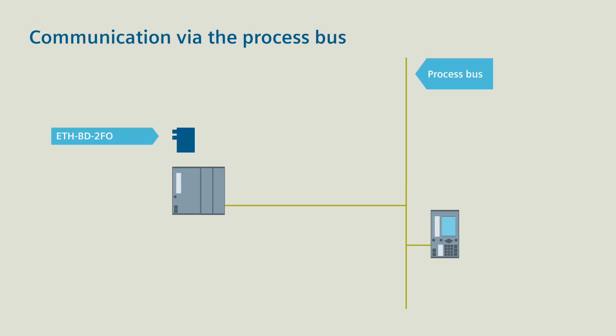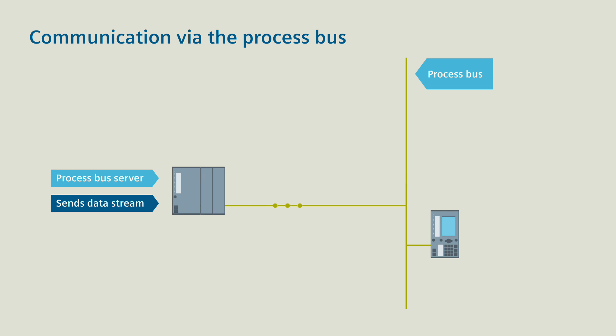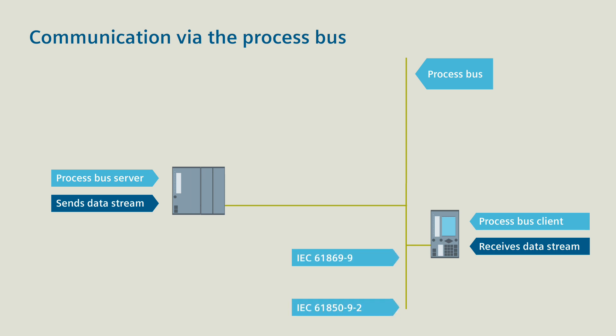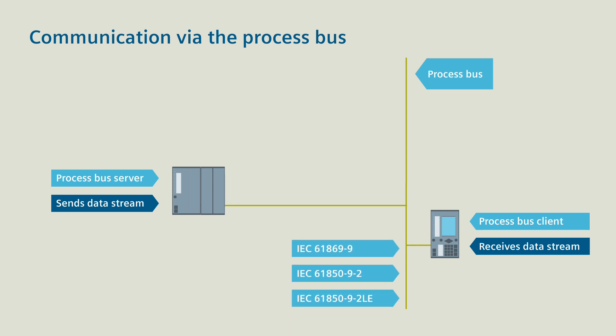The communication module installed in the SIPROTEC merging unit is configured as a process bus server. It sends a data stream of digitalized information to the SIPROTEC 5 device. In this device, the same communication module is installed, configured as a process bus client. In that way, the SIPROTEC 5 device is able to receive the data stream. All the usual process bus standards are, of course, fulfilled.